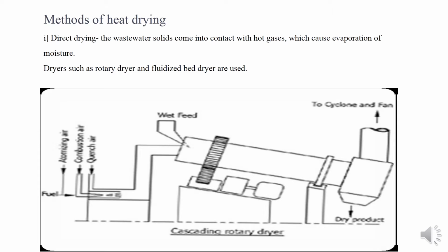For uniform distribution of sludge along the drum cross section, the drum is equipped with fins of various types. To break up and mix the sludge, there are also chains freely suspended at the beginning and at the end of the drum. The chains prevent the sludge from sticking to the walls at the beginning of the dryer and intensify the sludge drying process, and also avoid the necessity of having a dry sludge crusher in the system.